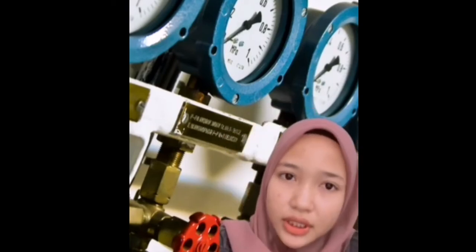The feed water pump takes a suction from the feed water tank and provides hot feed water directly to the boiler when the boiler's level control system sends a low operating water level signal. Feed water systems can maximize the life and efficiency of a wide variety of boilers. The feed water lines run from the feed water regulating valve station in the turbine building to the reactor building and hence to each steam generator.